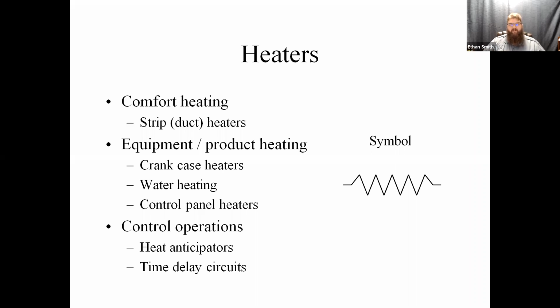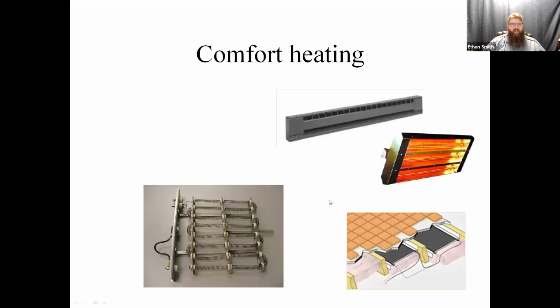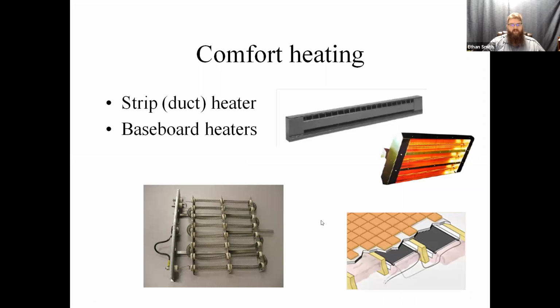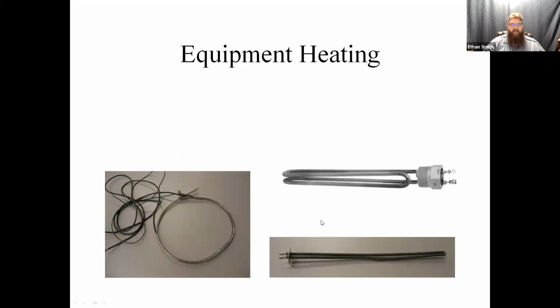Hydronic zone valves can be heat actuated controls. Okay. So the generic symbol for a heater in your electrical wiring diagrams is that little zigzagged line. Okay. We've got all the things we're used to seeing out there. We've got our standard electric heat, baseboards, radiant quartz, radiant in the floor, all that stuff. Okay. They're all just resistive heaters. More resistive heaters: crankcase, water heating elements. They're all just resistive heaters. This is just a giant resistor that generates heat.